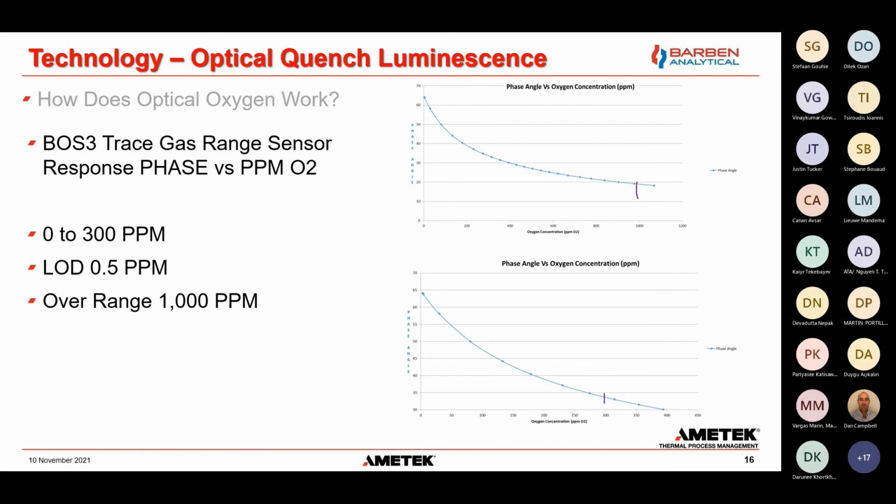We do go ahead and allow measurement after this, and this is what we call the over range. Is this range right here, but you see that it's a lot flatter, so we have less resolution, and we can't track very good. A lot of customers do like to still look at that range, but it is a little bit outside of our published accuracy spec, which is that 0 to 300 range.